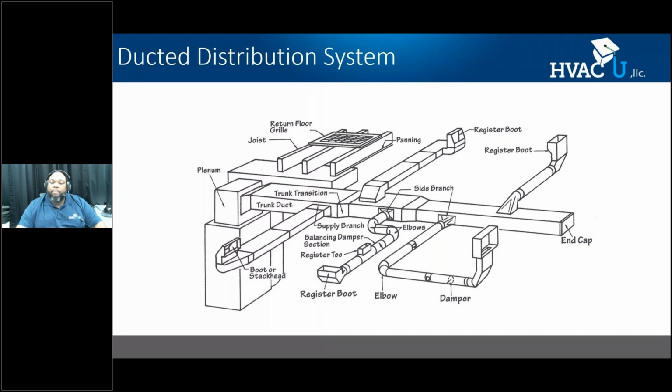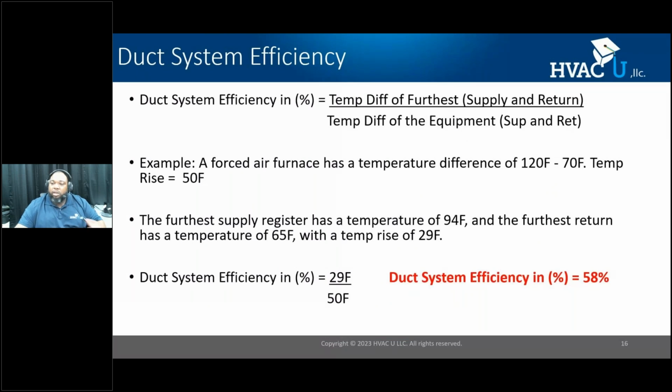So there's a couple measurements that we take. For years, technicians have always been trained to measure temperature rise at the equipment just to verify that the equipment is working correctly, but oftentimes we neglect the duct system, which is just as important as the equipment. Now, let's run through a scenario where you can use the duct efficiency to actually calculate how well the duct system is operating. So if we look at our formula here, I'm going to go back to the other slide so we can reference what we're talking about.